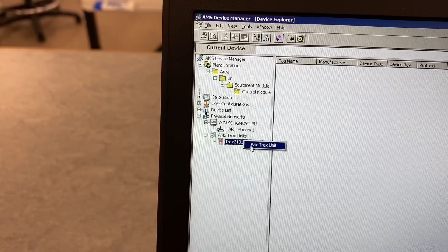So right now you can see on our Trex communicator, it's connecting to AMS and being paired. If we look over here now, the icon has changed, and there's a little green check mark on it indicating that it's been paired with our AMS database. All right, so now we've removed the AMS database from our transmitter here. You can see that it's kind of off on its own. It's disconnected. The HART modem has been removed.